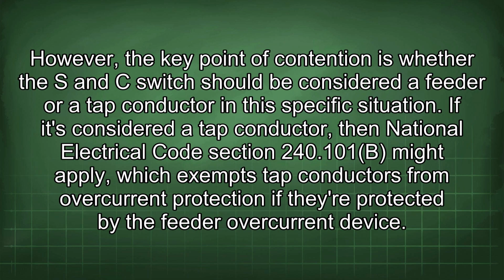However, the key point of contention is whether the S and C switch should be considered a feeder or a tap conductor in this specific situation. If it's considered a tap conductor, then National Electrical Code Section 240.101b might apply, which exempts tap conductors from overcurrent protection if they're protected by the feeder overcurrent device.